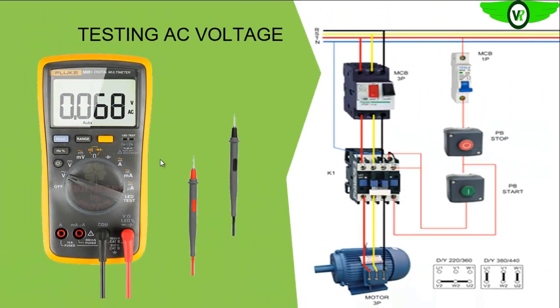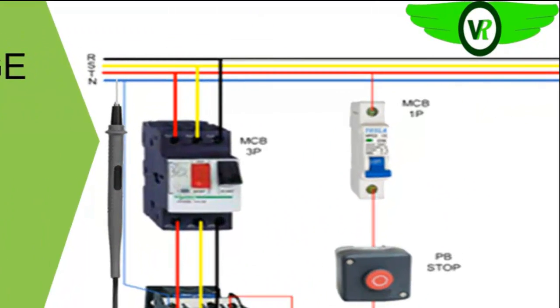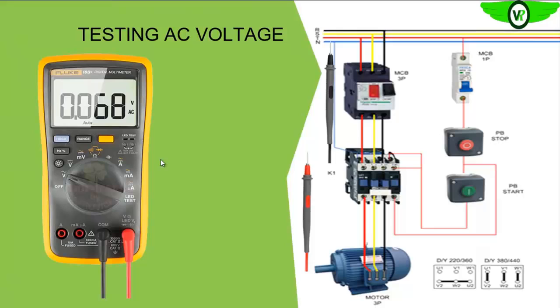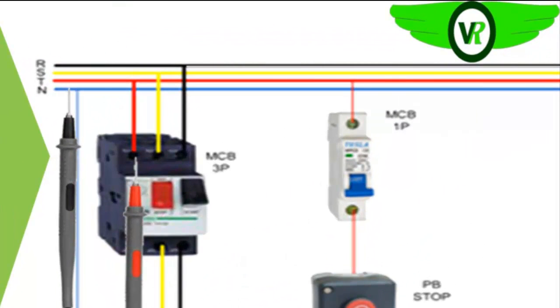So what do you do when you want to test for voltage? First, you move your probe to the neutral line, assuming you want to test the live line to neutral, the voltage that is on line to neutral. So first you move your black probe to your neutral line. Then you take your red probe to test the lines one after the other at the points that you can access. So here we can access the input to the circuit breaker in that particular circuit. So you take it, neutral to line 1, that is the red phase.